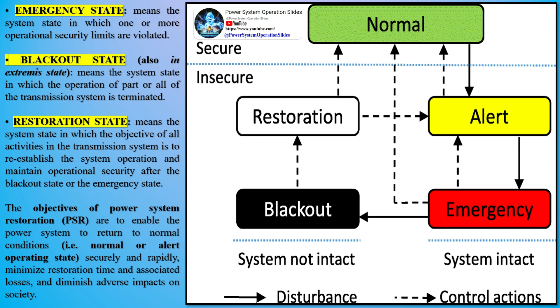Let's discuss bottom-up strategy. In bottom-up strategy, the initial energy is provided by, for example, a black start generator which performs the initial transmission network restoration. At this stage, the system is weak, i.e. the short-circuit current level is very low. After that, the island is expanded by connecting local load and generation. When sufficient generation is connected to the island, i.e. the short-circuit current level is sufficient, the restoration may proceed towards the high-voltage transmission networks.